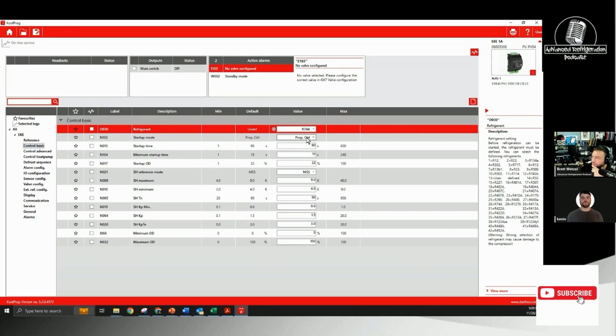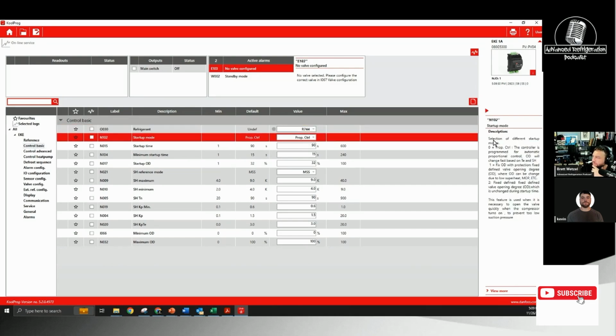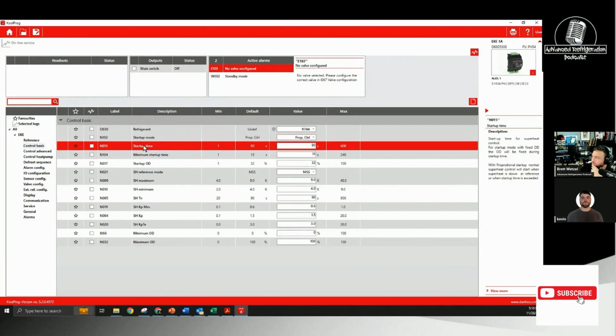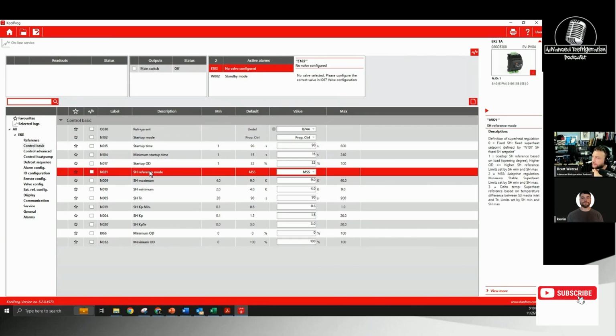So the nice thing about this, I believe when I was doing this, it gives a whole description of what it is, right? So proportional control, this controller is automatically programmed for the automatic proportional. OD will change fast based off the TE and the superheat. And so you have a definition with every single thing that you're doing. So startup mode, fixed during startup time, proportional startup, normal superheat will start when the superheat is down. Basically, you can go through and read through every single description when setting this up.